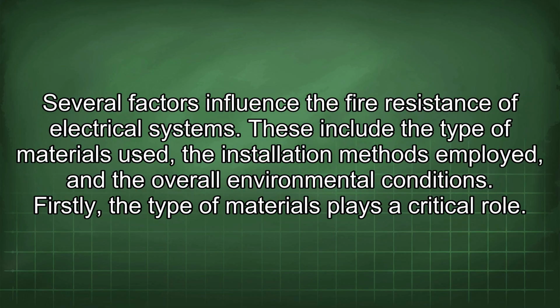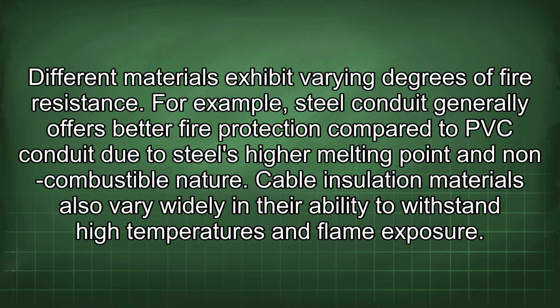Several factors influence the fire resistance of electrical systems. These include the type of materials used, the installation methods employed, and the overall environmental conditions. Firstly, the type of materials plays a critical role. Different materials exhibit varying degrees of fire resistance. For example, steel conduit generally offers better fire protection compared to PVC conduit due to steel's higher melting point and non-combustible nature. Cable insulation materials also vary widely in their ability to withstand high temperatures and flame exposure.